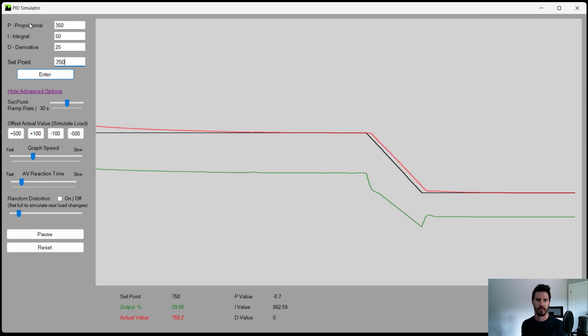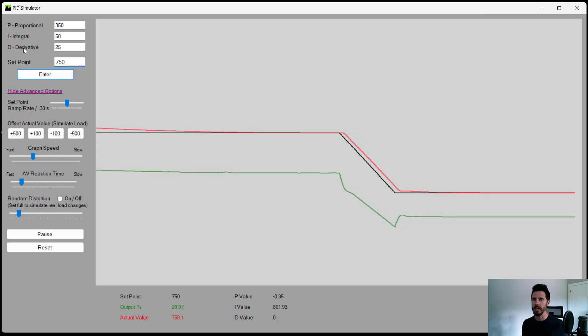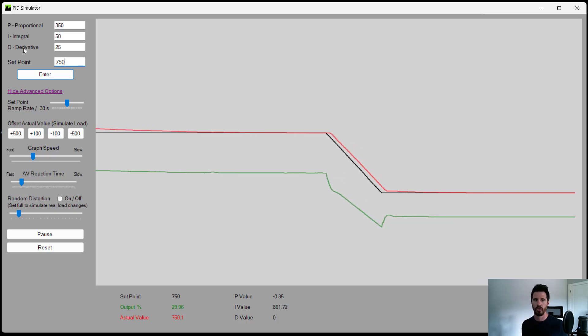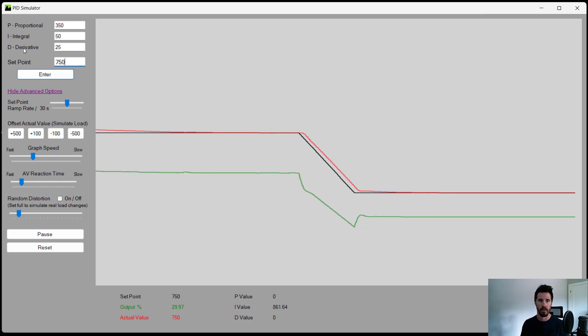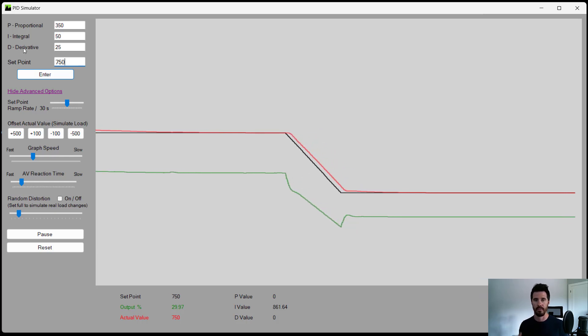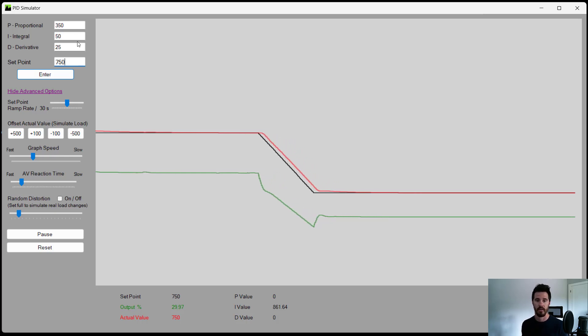Now, do note the multiplication factor or the gain on the P, the I, and the D may be different on your actual controller. Your controller might be 35, 5, and 2.5, or 3,500, 500, and 250, or it could be completely different.